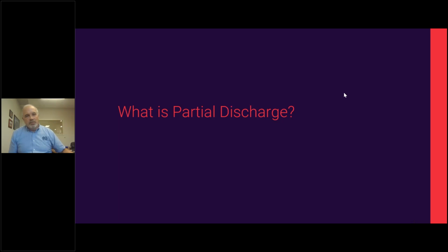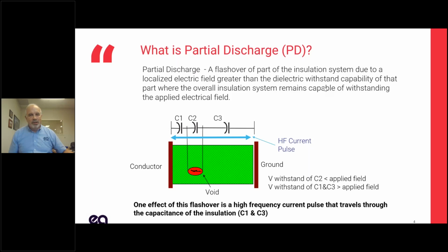So the first question is, what is partial discharge? A lot of people are not familiar with it. A lot of people think they're familiar with it, but have been told a variety of different stories over time. But let's get into it. The Wikipedia definition is that partial discharge is a flashover of part of the insulation system. It is a flashover, but not of the entire insulation system, otherwise you'd have a catastrophic arc flash. This is due to the electric field being greater than the withstand capability of that part of the insulation.